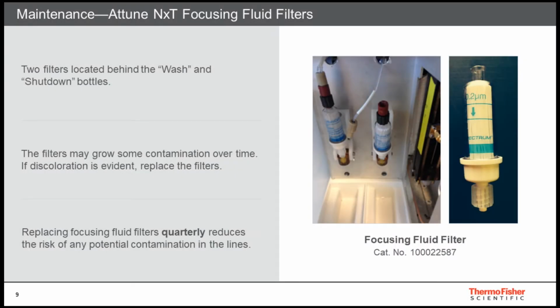The 2 focusing fluid filters in the fluidic compartment must be replaced every 3 months, ideally after the system decontamination script. However, in case of heavy usage, please replace the filters more often. The filter may grow some contamination over time or may get clogged. If you see any brownish red spots, it is highly recommended to change the filters immediately. If the filter is intact, it should keep growth out of the system. However, filters can rupture, and running the system decontamination script to decontaminate the system is highly recommended. During normal operation, if the focusing fluid pump takes long to fill the focusing fluid container or times out, change the filters immediately.